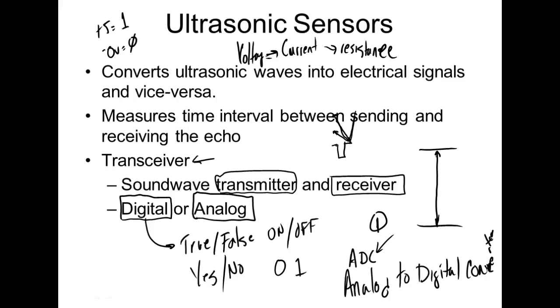Usually if it's a digital signal, that's what we have the ability to do, and we'll look at this when we go over there. If you look on the sensors, just about all of them have a little screwdriver setting in there. So what you can do is adjust that screwdriver and set what we call the threshold. You're saying, okay, if it's above this threshold, send my computer a 1, or a voltage. We say a 1, but actually all it's doing is sending out a voltage. Now we took a physical stimulus and converted it over to a voltage, and now I can send that into a computer.